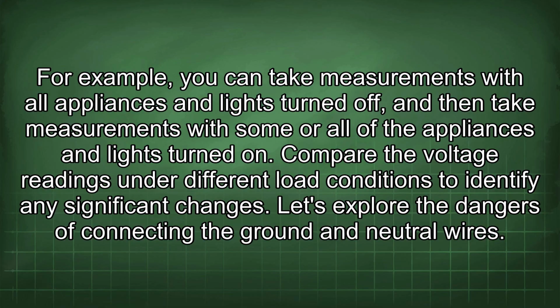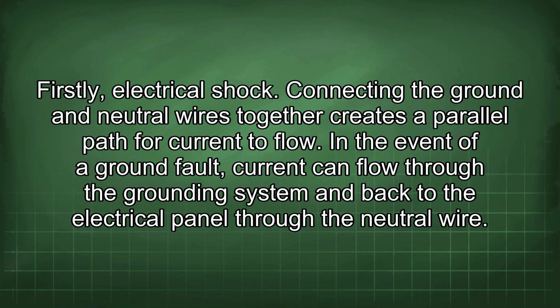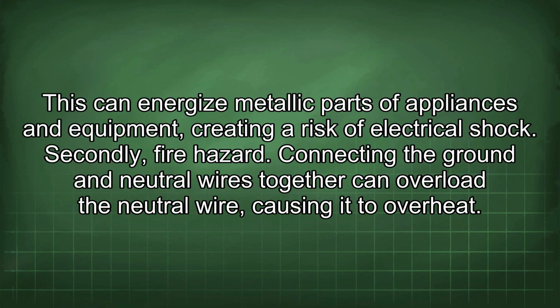Let's explore the dangers of connecting the ground and neutral wires. Firstly, electrical shock. Connecting the ground and neutral wires together creates a parallel path for current to flow. In the event of a ground fault, current can flow through the grounding system and back to the electrical panel through the neutral wire. This can energize metallic parts of appliances and equipment, creating a risk of electrical shock. Secondly, fire hazard.